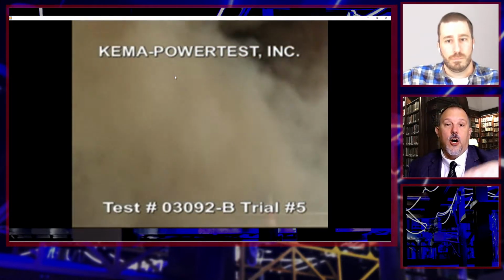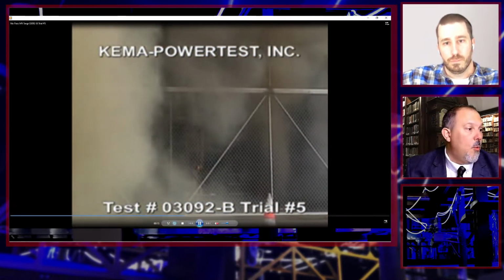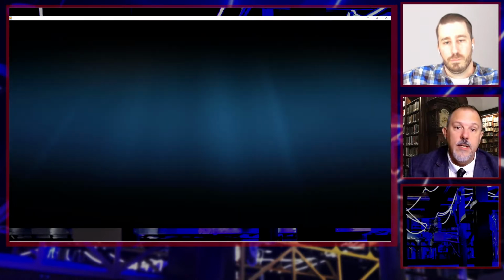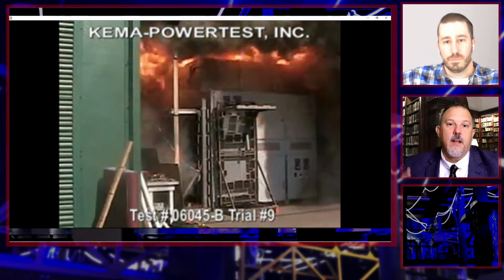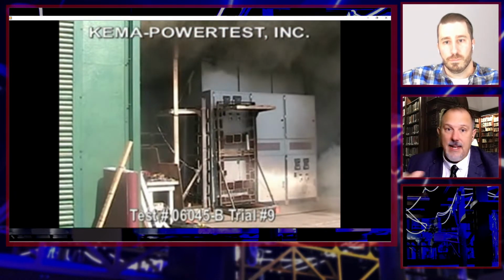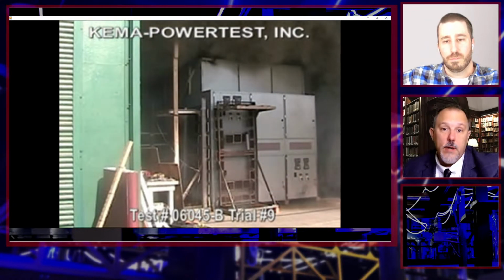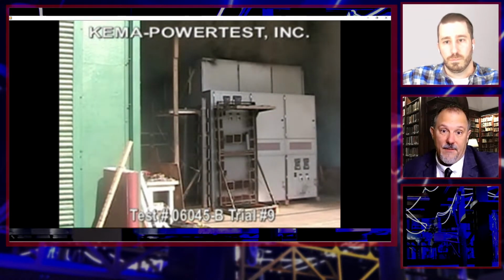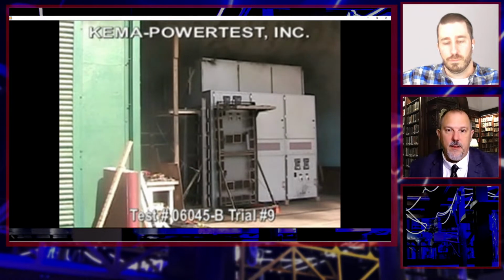In this arc resistant equipment, what we are going to do is take that energy and make sure we funnel it up. It's the same amount of energy. If that was a 40 cal event, it's still a 40 cal event, but we're not letting it come out the front of the equipment.